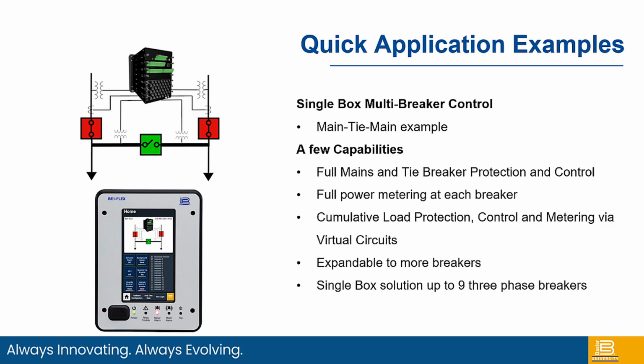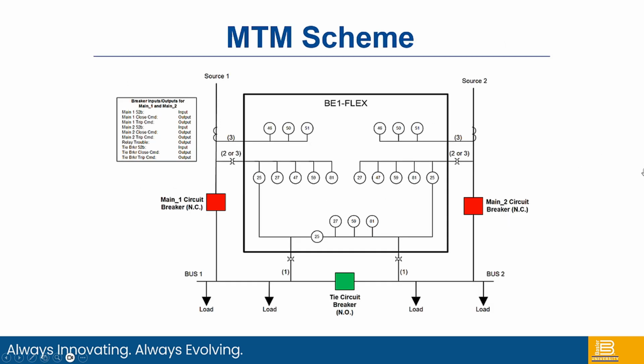lots of different ways you can mix and match, again giving so much performance and capability to the designer and the operators to do what they want as opposed to being fixed into a box that's set for a specific application. And here's the main-tie-main in a little bit more detail. In these applications, we're looking at voltage oftentimes on the 2 sources, as well as both sides of that tie breaker on the bus, and that allows sync check to occur across this breaker, sync check across this breaker, as well as this breaker.